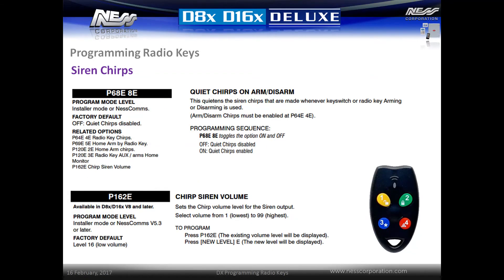Activating option p68e 8e will reduce the siren chirp volume by about half. Optionally, a new option in the latest version D8 panels allows siren chirp volume to be set specifically. Enter option p162e, then enter the chirp volume between 1 and 99, with 1 being the lowest and 99 being the highest.